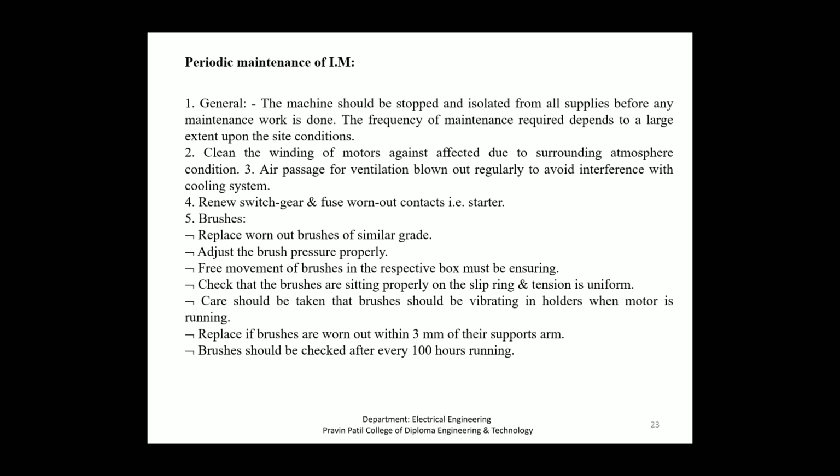Check the commutator for smoothness. The next, examine connection between commutator and armature coil. Next, test insulation by megohmmeter. Next, check air gap. This is the periodic maintenance of induction motor.